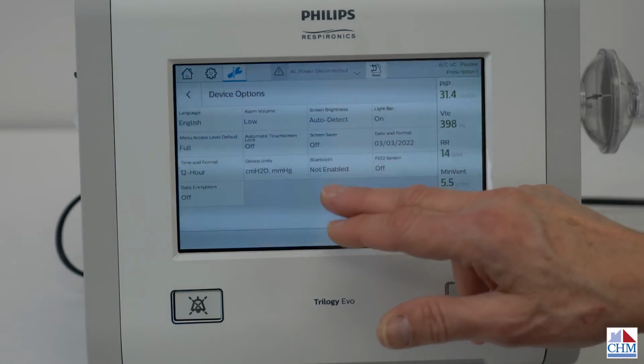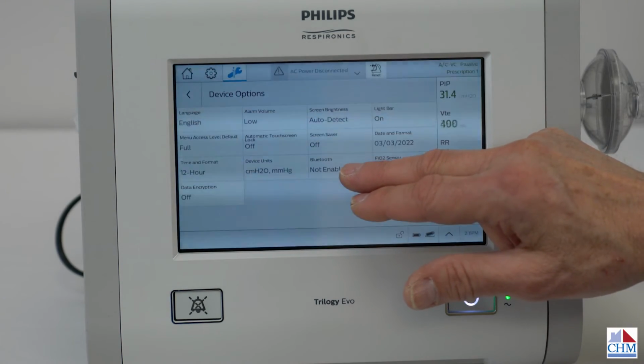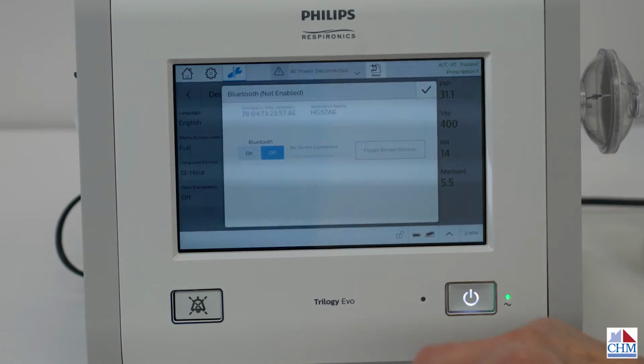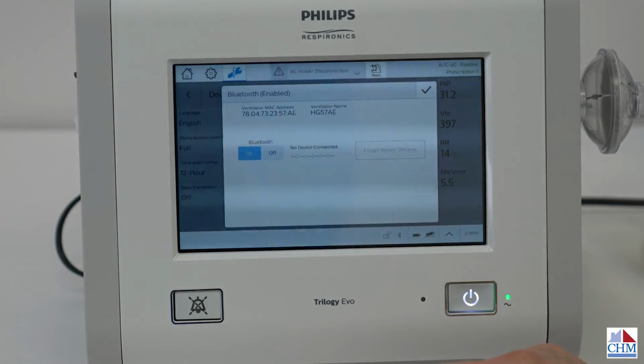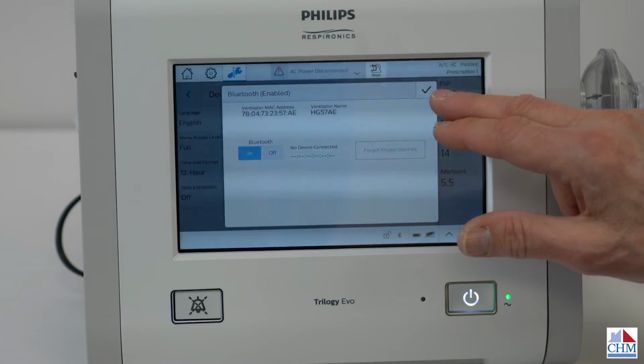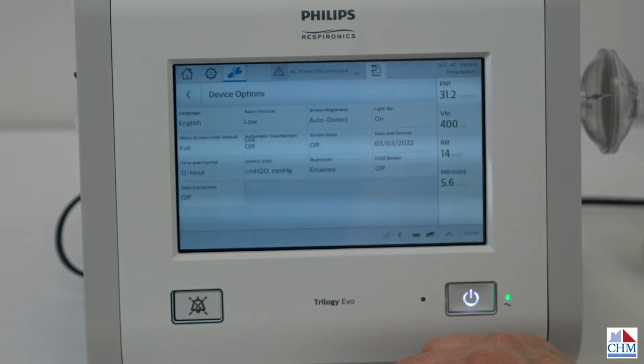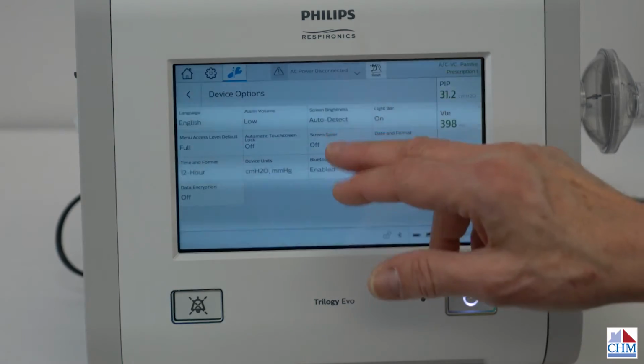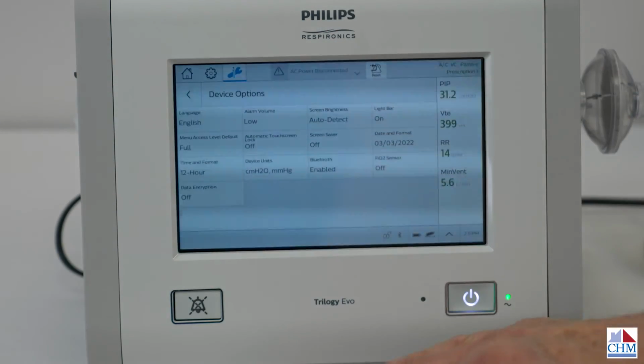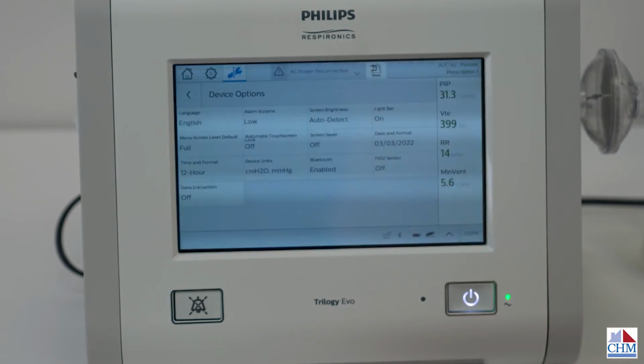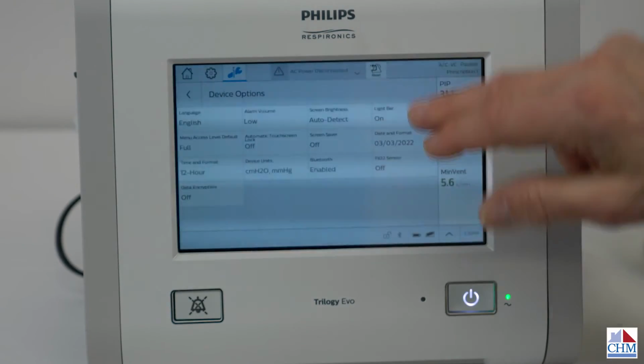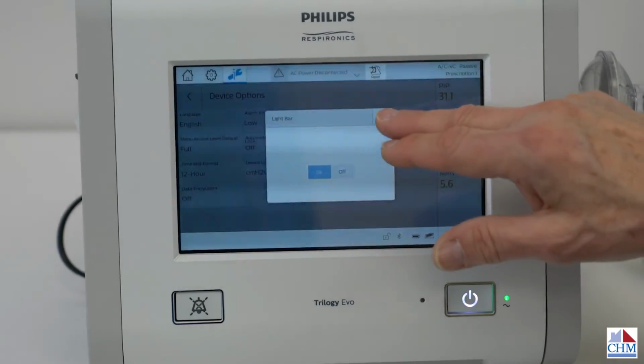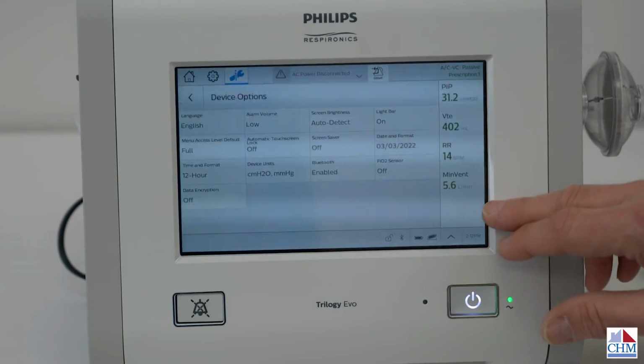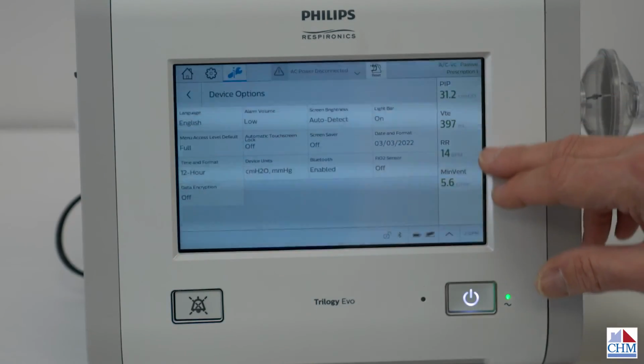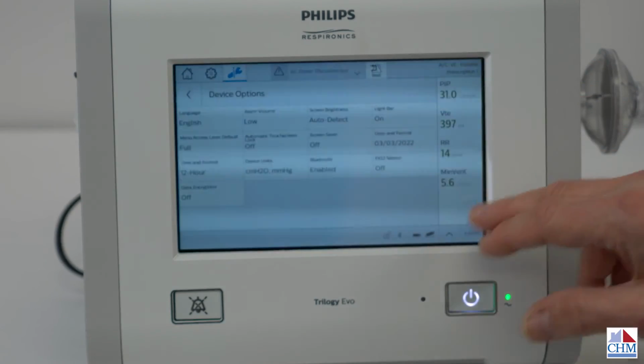But you can see if we wanted to enable Bluetooth, if we wanted to turn that on, I would turn that on here by hitting the touch screen and hitting the on button in order to turn on Bluetooth, and then hit the check mark to accept it. So now Bluetooth is enabled on this one. We can add a screensaver so that the screen goes dark or dim, whatever we want to do. And that light bar for the alarm up here, we can turn on and off by using this. So we'll leave that on for right now. Notice while the vent is running, we're actually displaying some parameters over here too, so we can keep track even while we're in the menu of how the patient is doing on the ventilator.